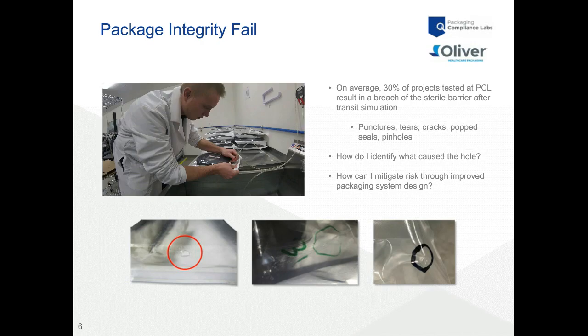The dreaded outcome for packaging engineers is when a hole or breach of the sterile barrier is identified in bubble leak testing—that's what we'll talk about today. What should you do when you identify a hole? How should you investigate to determine the root cause and mode of failure? We're also going to show slow motion footage of flexible and rigid packaging behavior inside shipping boxes during drops and vibration, and discuss how that behavior relates to potential failure modes.